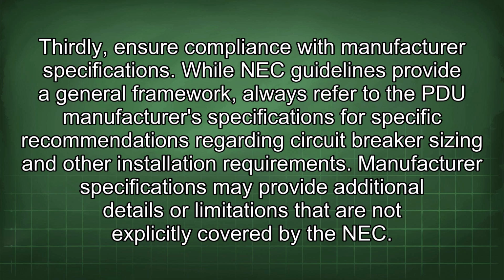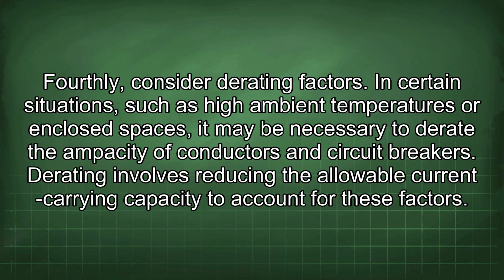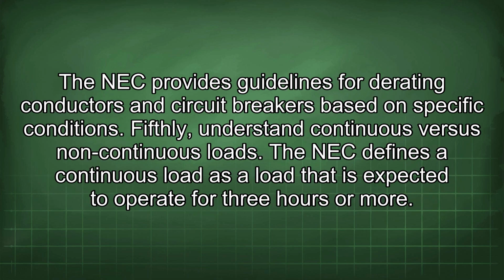Thirdly, ensure compliance with manufacturer specifications. While NEC guidelines provide a general framework, always refer to the PDU manufacturer's specifications for specific recommendations regarding circuit breaker sizing and other installation requirements. Manufacturer specifications may provide additional details or limitations that are not explicitly covered by the NEC. Fourthly, consider derating factors. In certain situations, such as high ambient temperatures or enclosed spaces, it may be necessary to derate the ampacity of conductors and circuit breakers. Derating involves reducing the allowable current carrying capacity to account for these factors. The NEC provides guidelines for derating conductors and circuit breakers based on specific conditions.